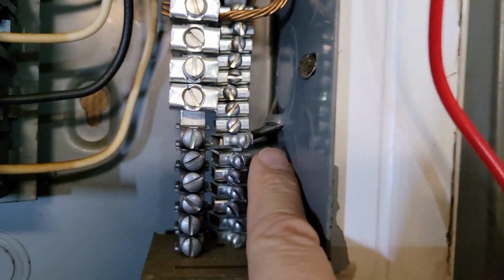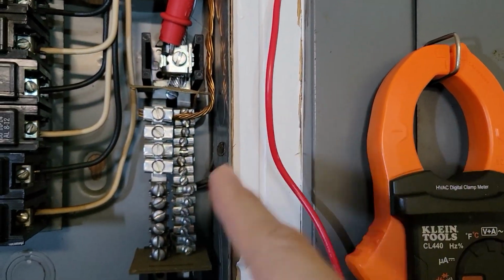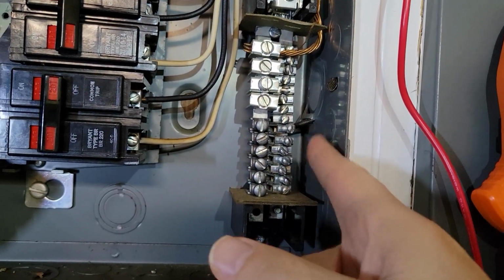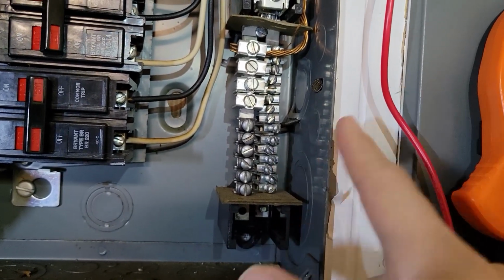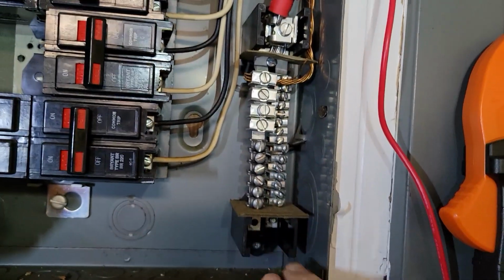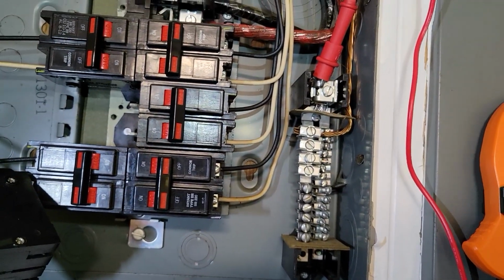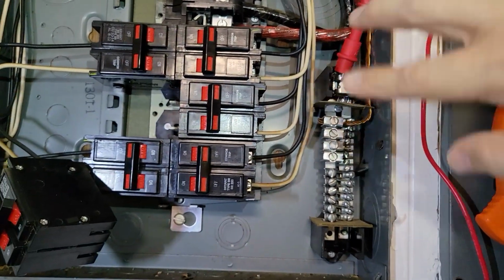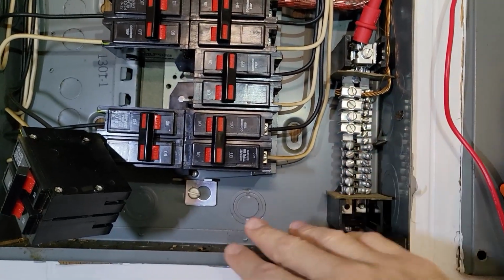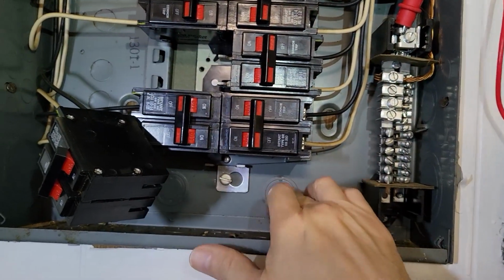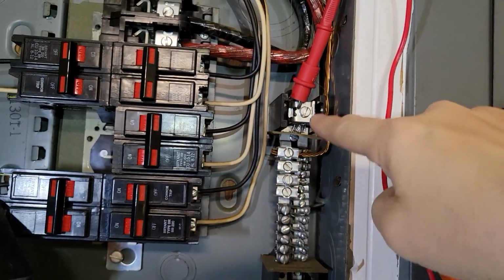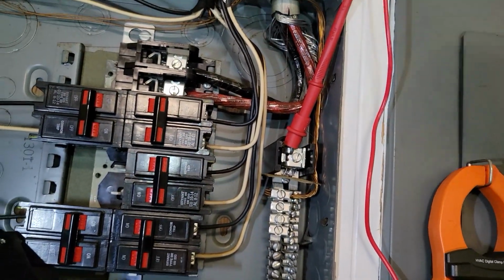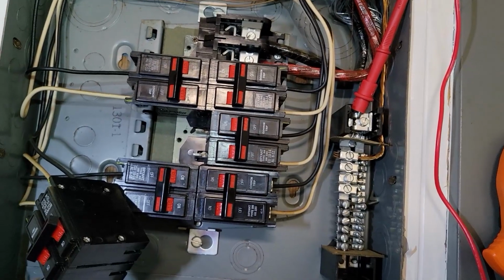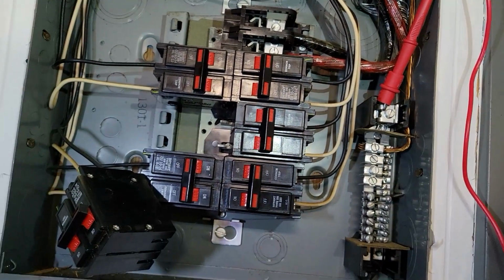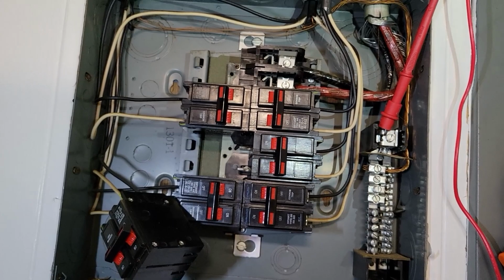And also there's this weird thing where there's a nail coming through here from this box, and that needs to be disconnected because that's just causing these two to bond together, and that's not a wise thing for it to do. So if I get this done right, the ground will be going on its own bus to the case. The neutral will go back to the main circuit breaker, and there it gets bonded with the ground because that's the way it's supposed to work. So hopefully I can execute that.